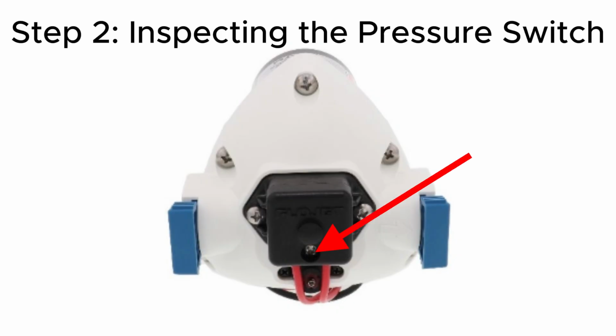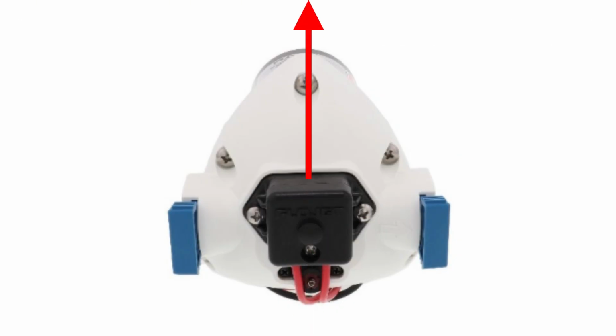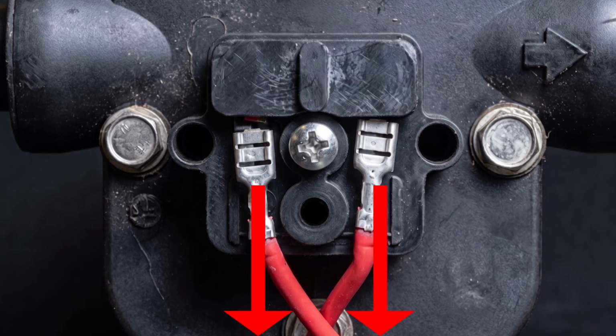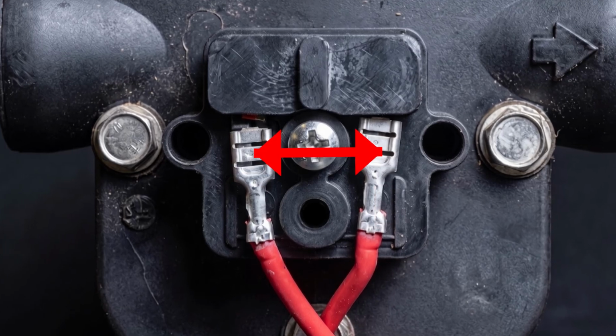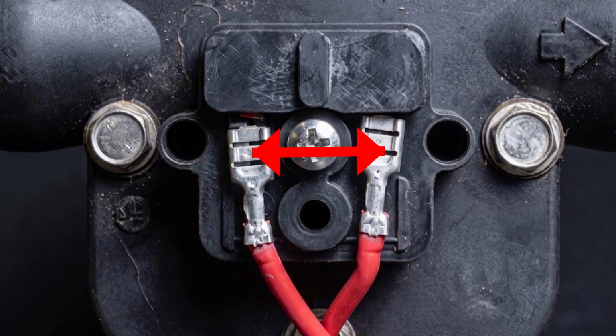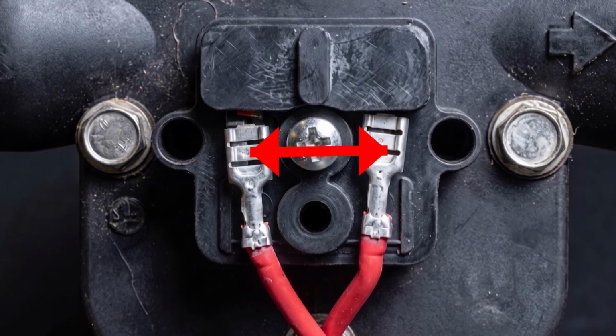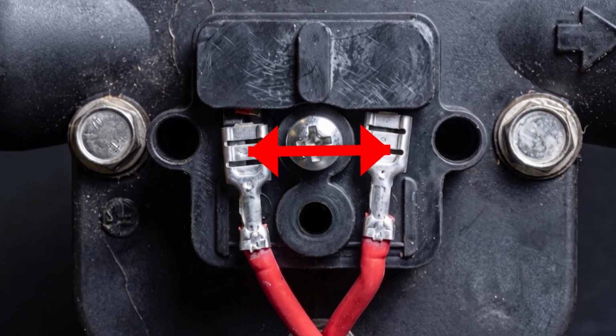Remove the small screw on the pressure switch cap and lift it off. Gently pull the two wire spade connectors off their metal tabs and touch them together. Turn the power on to the pump. If the pump turns on, that means the pressure switch was the problem and should be replaced.